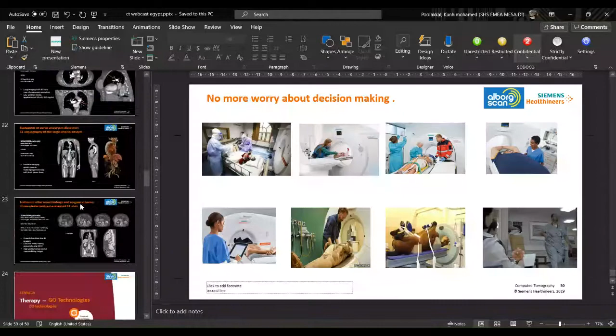To answer this question, most of the vendors have a filter to reduce the unwanted quanta to the patient. That is called the aluminum wedge filter. What Siemens has done, I can again share my screen and show you, is that we additionally put another filter on the system. I can just go to that slide and show you that. Is it able to see my screen? So here, you see that additional bow tie filter. We have a patented technology called the tin filter. That will allow us to reduce the dose drastically.